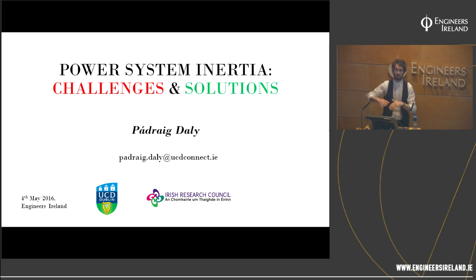And that gets hairy, because frequency is no longer a concept. We have a grid frequency because the synchronous generators are rotating in synchronism, and they inject voltages and currents at 50 hertz. That's why we have a 50 hertz system. If you don't have any conventional power plants, you don't have a frequency. So that's totally different stuff. But you're definitely not going to say it can't be done.